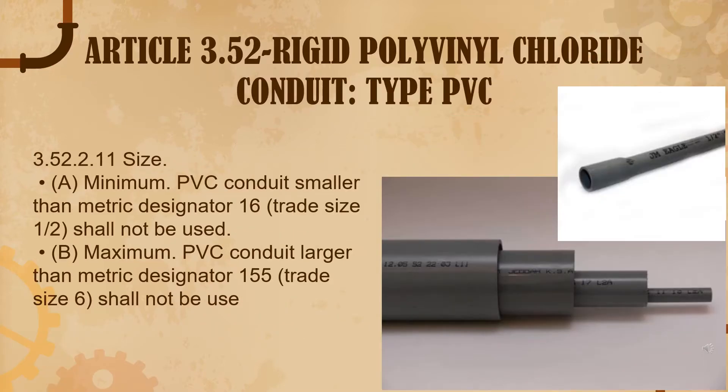Article 3.52, Rigid Polyvinyl Chloride conduit. This can be found on page 230 of PEC 2017. Under 3.52.11, the sizing: the minimum conduit smaller than 16 mm trade size 1/2 shall not be used. And the maximum, larger than 155 mm trade size 6, shall also not be used.